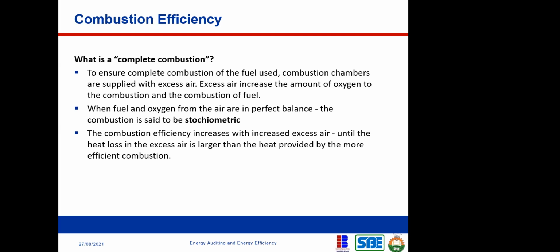Now, because you don't know the exact amount of air that you can add to deliver the right quantity of oxygen, remember that you're adding air because of the oxygen that is in the air, right? And air has about 21% oxygen, about 78% nitrogen and so on. But you don't know the right amount of air that will enable the fuel to burn completely. So it is advisable that you add excess air. Instead of achieving under combustion, it's better to have more excess air. Okay, but too much excess air is also bad. So there are ways to measure some of these things. Anyway, I will come to that. But I'm just trying to introduce you to the concept of excess air, and why you need to add excess air to your combustion process, just to make sure you achieve a complete combustion.